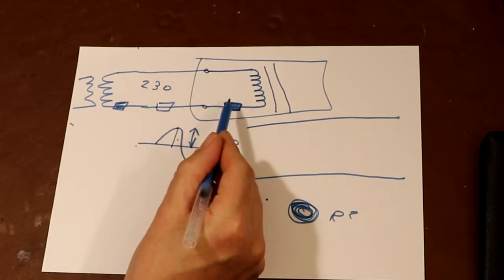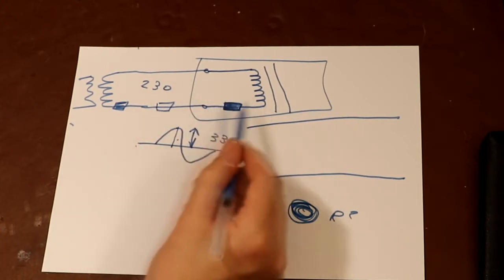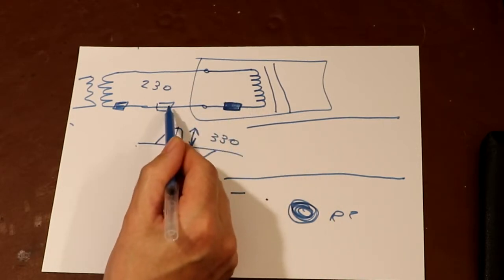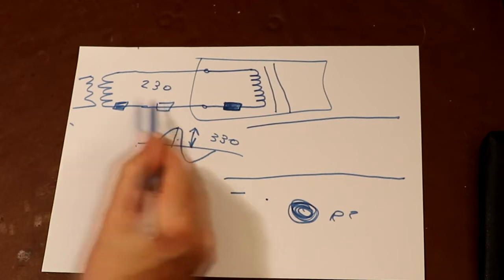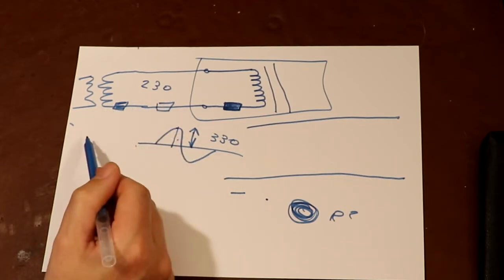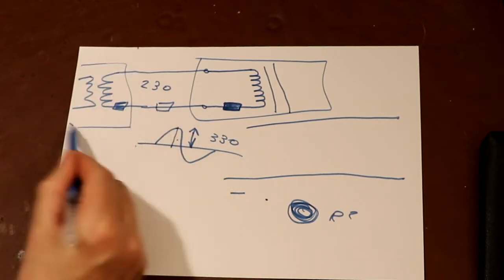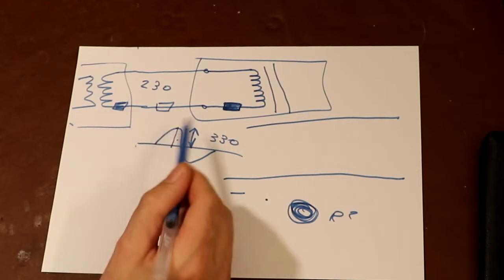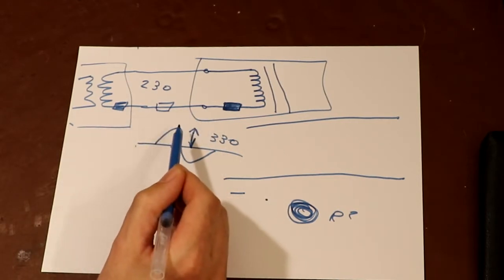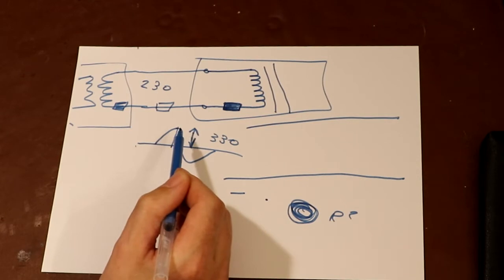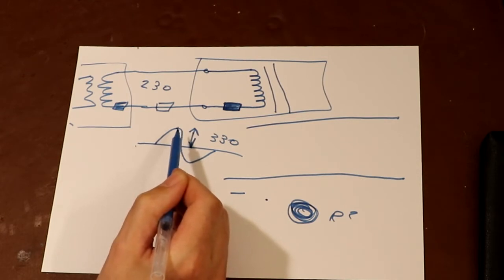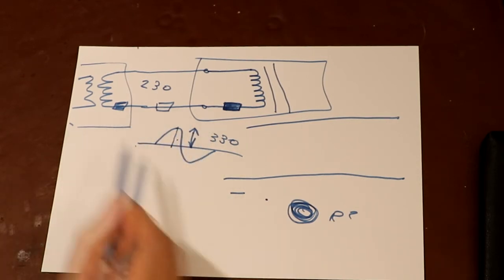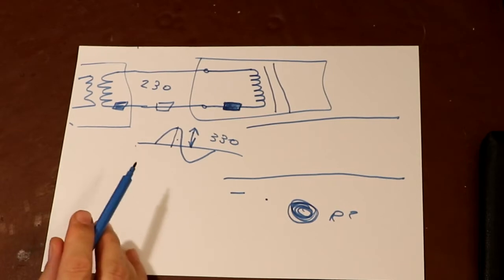So what's actually limiting the inrush current? It's the winding resistance, plus the supply impedance from the wiring, plus the transformer impedance from the distribution transformer. We can actually crudely measure some of that and see if we get the right kind of figures. Let me go ahead and have a go at that, and let's see what the figures come out at—I don't know if it'll work, I'm just interested to see myself.